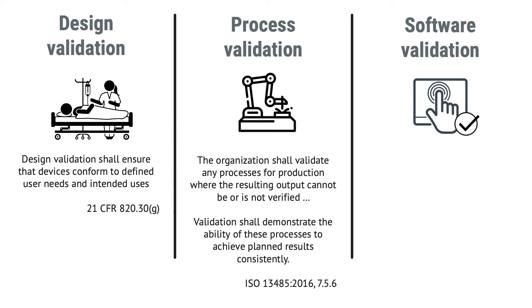Process validation is about validating any processes for production where the resulting output cannot be or is not verified. Process validation shall demonstrate the ability of these processes to achieve planned results consistently. When talking about software as a medical device, process validation of the production process is typically not applicable to SaMD.